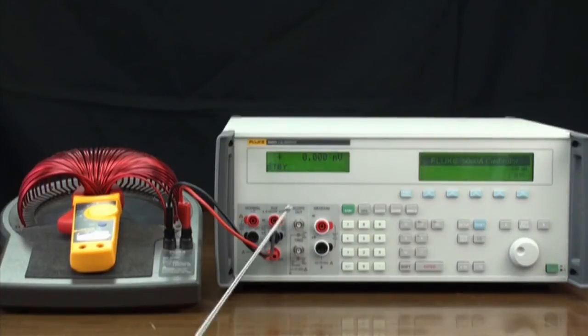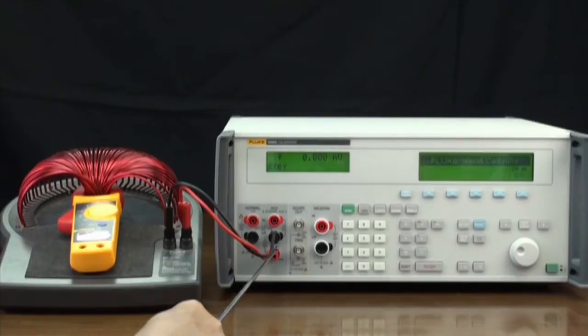Connect the current coil to the 5080A Calibrator. Use the 20 Amp Terminal and the Aux Low Terminal to output currents of 5 Amps. 3 Amps and above require the use of the 20 Amp Terminal.